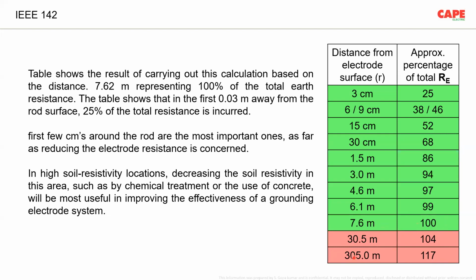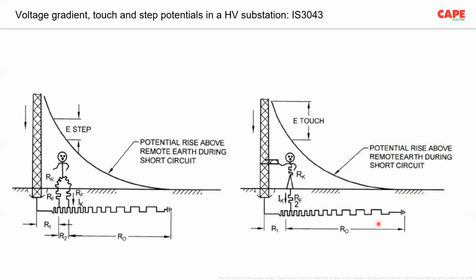So a 270 meter increase gives only about 15% improvement. So these are considered insignificant. As a result, we think that the 100% is the RE value, which is received within a typical area of 7.6 meters. This is only an example, but from place to place it varies. It depends on the soil resistivity, basically. For high voltage application, anything more than 1 kV, of course, you have the step and touch voltage problems, which are explained in the IS 3043.